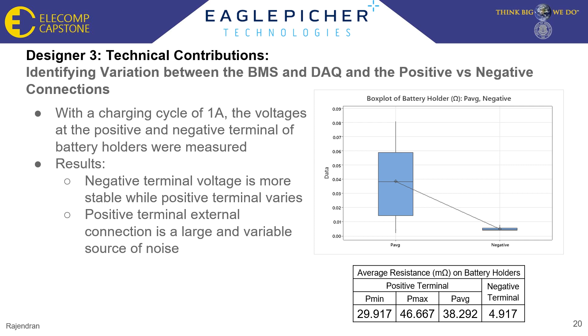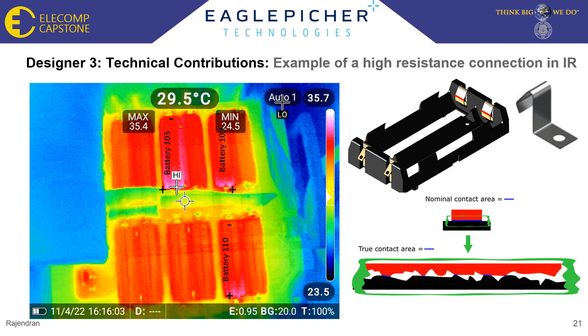To further prove this, the thermal image on the left shows batteries 105, 109, and 110. The positive terminals have higher temperature compared to the negative terminals. The high resistance is caused by the contact between the battery and the battery holder terminals, as you can see in the nominal contact area versus the actual contact area.